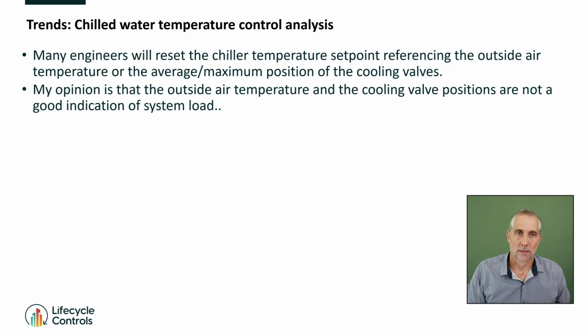In the old days, 20 years ago, we didn't reset the chill water pressure set point. We didn't do that. So the chill water pressure set point was fixed at say 200 kPa, 200 kilopascals. It was fixed. The pressure in the system didn't change. Okay. In those days, the position of the cooling valve was a true indication of the load. So if the cooling valves were mostly open, it's a warm day, there's a high load. If the cooling valves were mostly closed, it wasn't a high load, it wasn't very hot outside, there wasn't a lot of people in the building, we need less cooling.